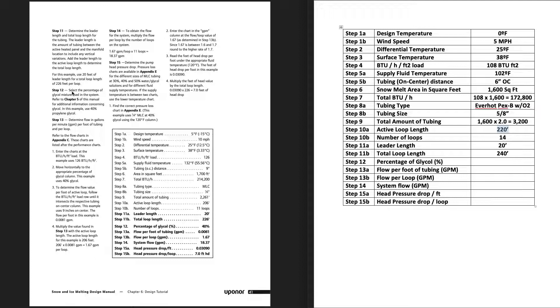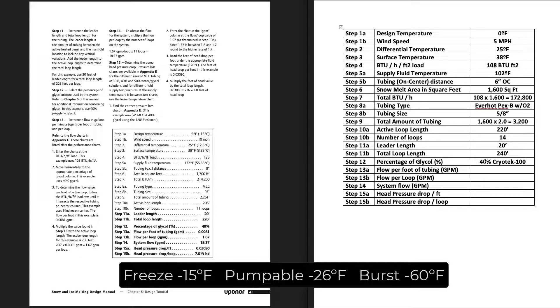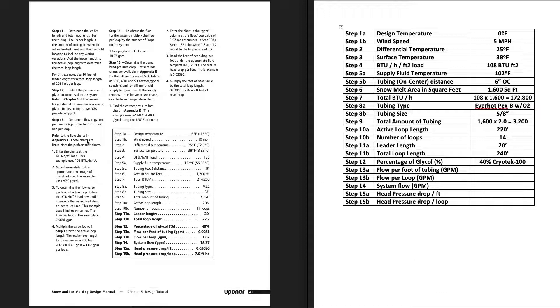Step 12: determine your glycol percentage. I used a 40% mixture of Cryotek-100, which provides even a bit more freeze protection than some other brands — I believe freeze protection to around -15°F, movable to around -20 or -30°F, and burst protection to around -50°F. That's plenty of protection here in Buffalo, New York.